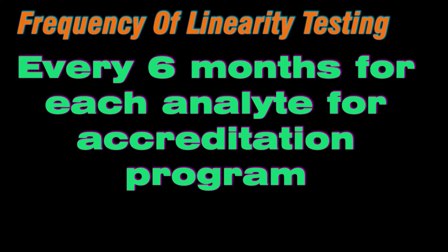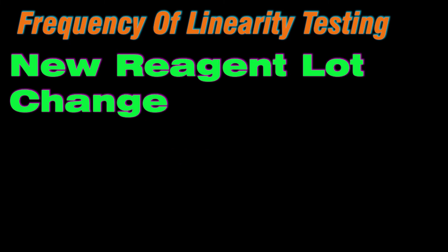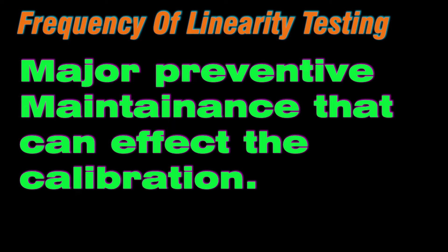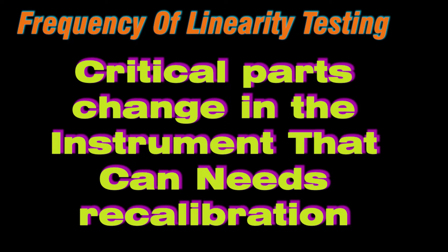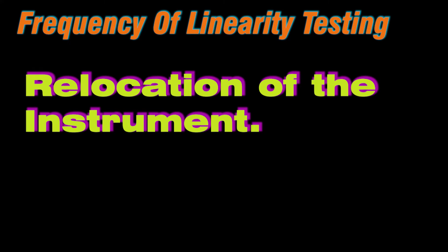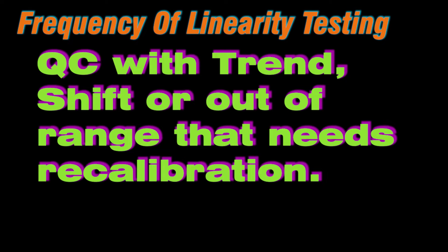How often should linearity or calibration verification be run? If our lab performs calibration verification every six months, we do not have to perform it separately for any laboratory accreditation program. Otherwise, we need to perform it every six months, whenever there is a complete change in the set of reagents to a new lot, when there is major preventive maintenance or replacement of critical parts of the instrument, or when quality control data shows a drift, trend, shift, or QC outside acceptable limits.